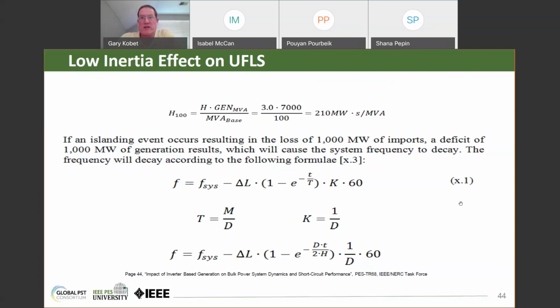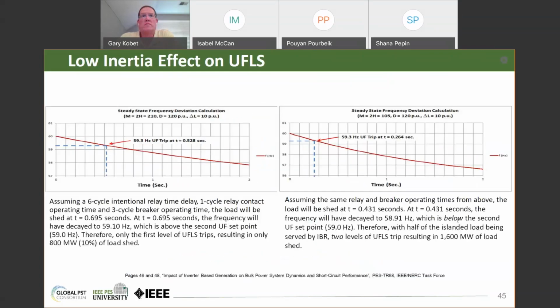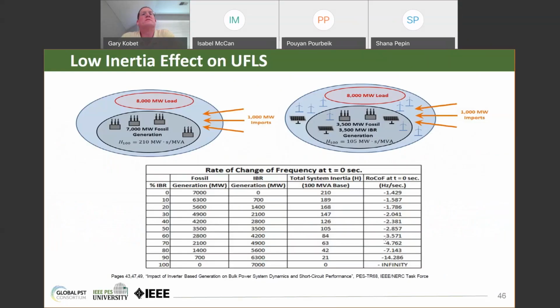The next slide shows two different examples for two different inertia constants, total inertia for the system. On the left, the total inertia is 210, and the rate of change of frequency for that, I don't think I know the exact rate. I'd have to calculate it, but you can see the frequency decline, and there's a table on the next slide that actually shows the actual rate of frequency decline. But with the inertia, thank you.